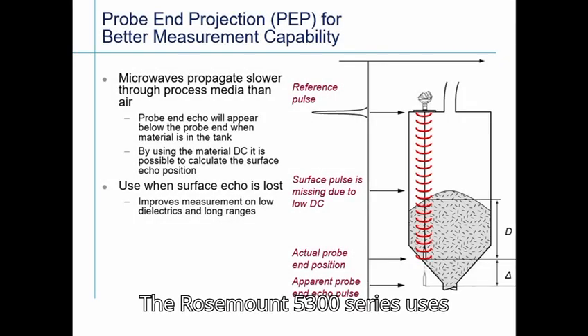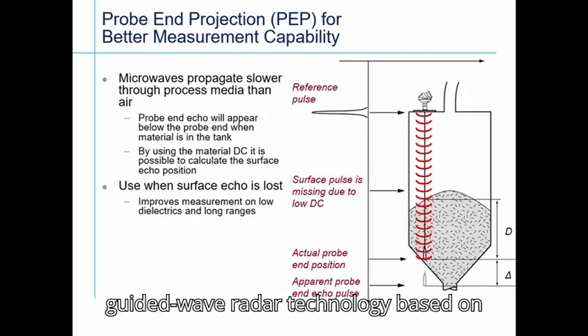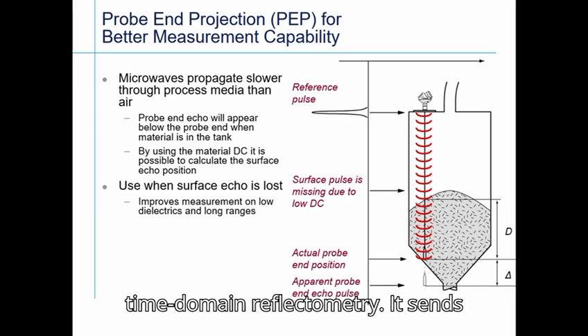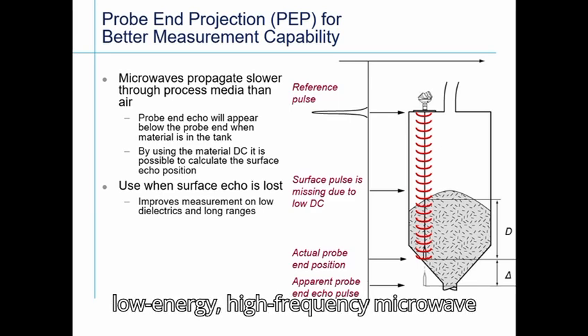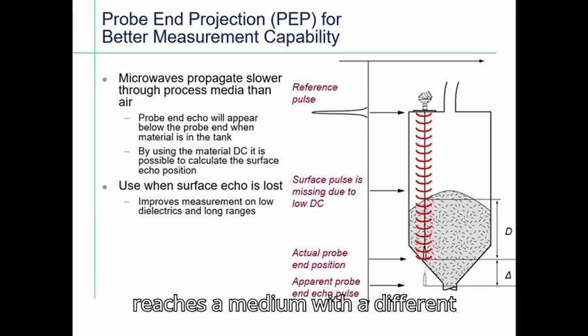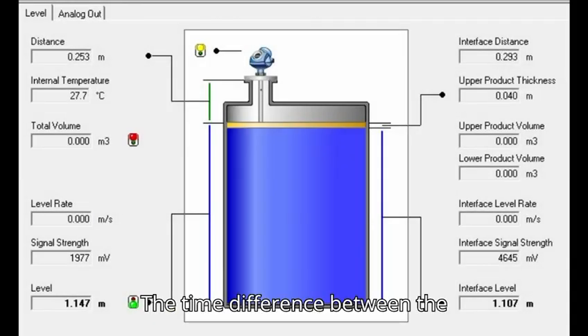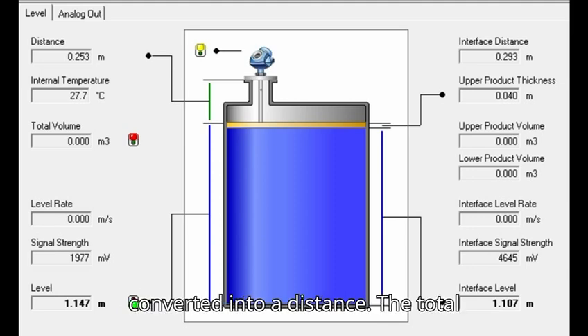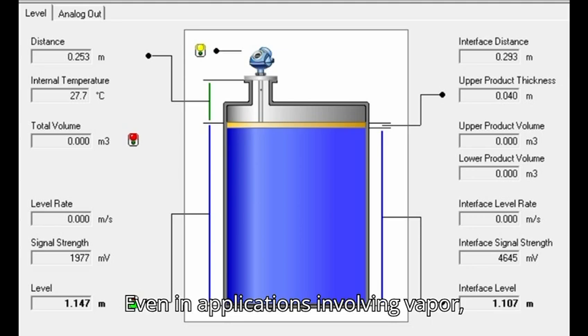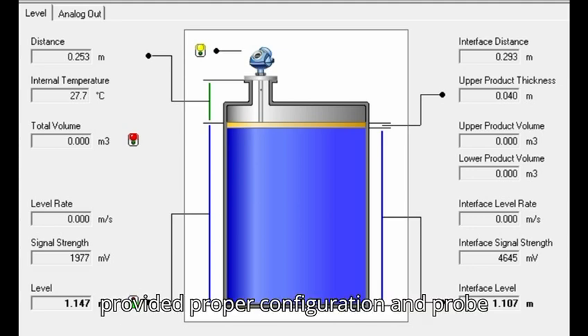The Rosemount 5300 series uses guided wave radar technology based on time domain reflectometry. It sends low-energy, high-frequency microwave pulses down a probe. When the pulse reaches a medium with a different dielectric constant, part of the signal reflects back to the transmitter. The time difference between the transmitted and reflected pulse is converted into a distance. The total level or interface level is then calculated. Because the signal travels along a probe, GWR is very stable, even in applications involving vapor, turbulence, or changing liquid interfaces, provided proper configuration and probe selection.